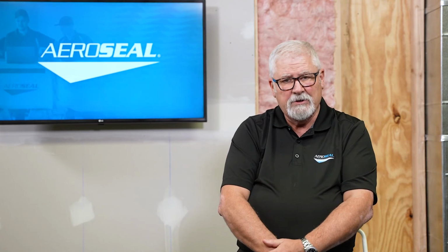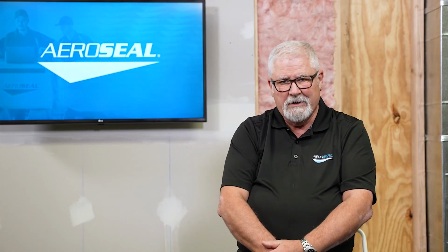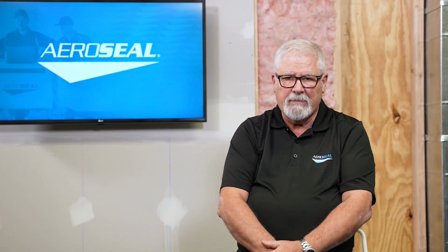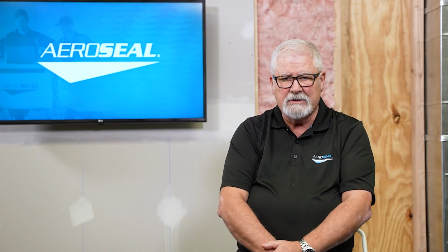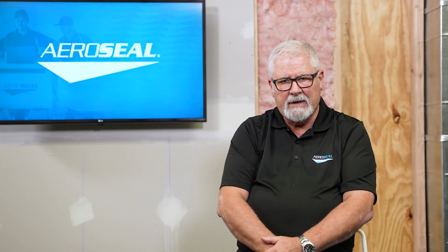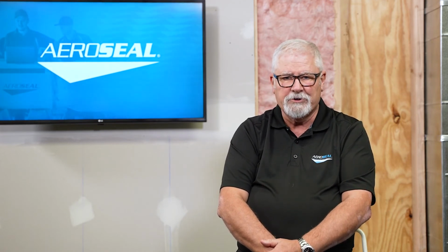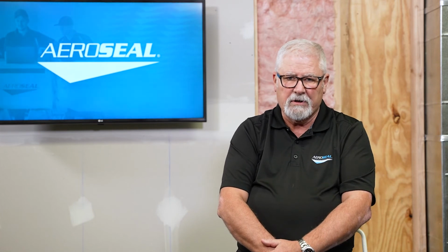Okay, we're back in the studio, and as you saw the house we just worked on, well, that was a pretty big job. What we had to do is get inside. We found some major leaks in those return chases. We got some Corex board in there. We bent it, we cut it, we jammed it into space, and of course we took mastic with paintbrushes and sealed it down tight. All we wanted to do was make that duct system so we could build up a pressure and then Aeroseal it with our Aeroseal system. It was a lot of work, but we were able to get it done.